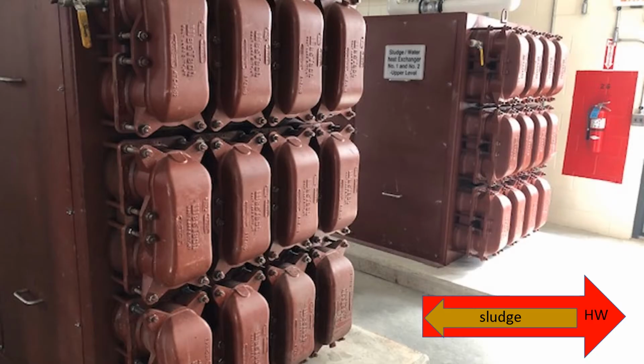The sludge heat exchangers are operated in parallel, meaning there's one heat exchanger for each digester. The heat exchangers are shell and tube, so essentially a pipe within a pipe. The inside pipe is full of the digested sludge, constantly being pumped and recirculated. Flowing the other way is hot water from the heating loop system, and the hot water is basically trying to maintain a sludge temperature of the 95 to 98 degrees required for the mesophilic bacteria.